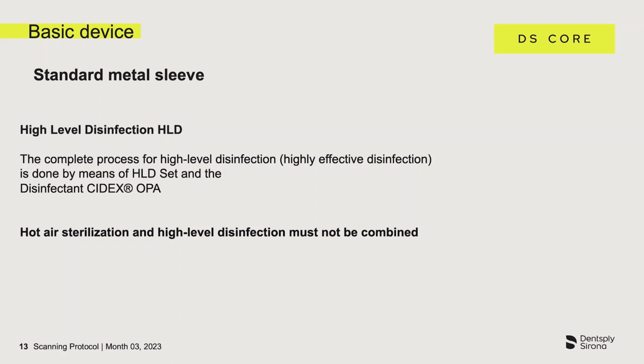Now the sleeve must be attached to the plug while the metal bracket is held to ensure that no particle contamination or liquids penetrate the inside of the sleeve. When properly attached, the stopper closes the sleeve. The high-level disinfection container is carefully filled to the mark and then inserted using the metal bracket with the sleeve. The sleeve must remain in the disinfectant for at least 12 minutes.